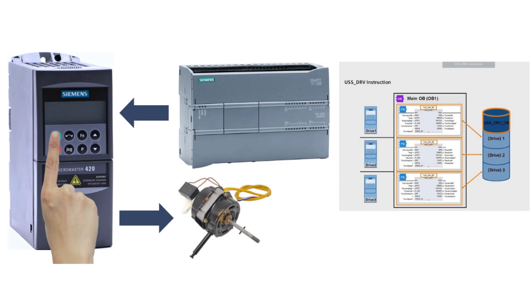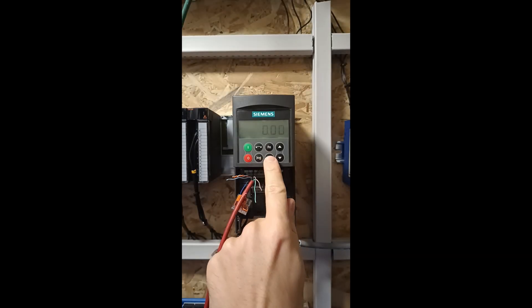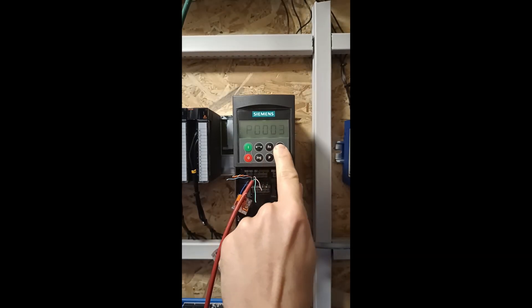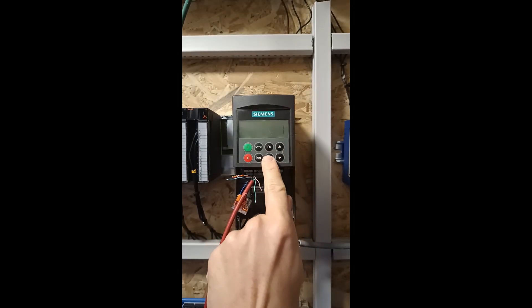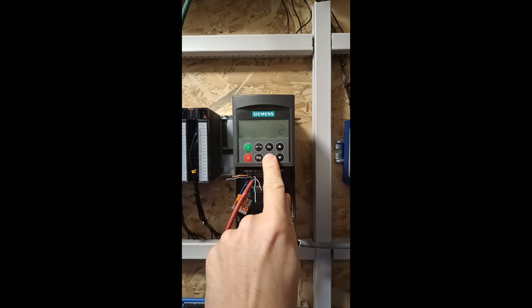First let's go through how to do the settings on the VFD. First we want to set parameter 3 to 2. This will allow us to do the RS-485 settings.